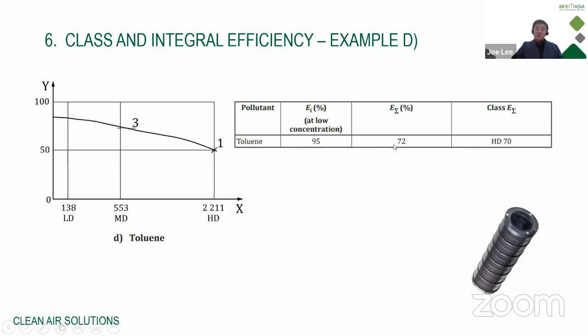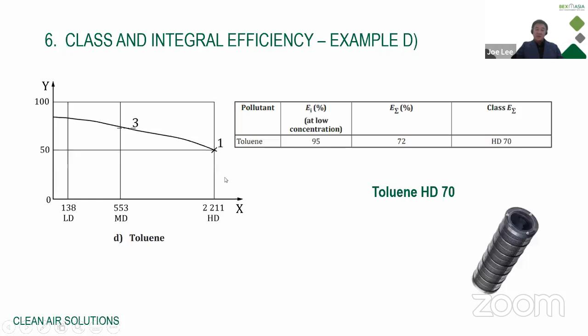And when we pump more into the filter, at the HD level, you can see the filter actually drop below 50%, so we stop the test from here. The average efficiency from initial to this point where it dropped below 50% is about 72%. So we have to classify this as 70% HD, because the drop point is after HD. So this filter is classified as heavy duty.